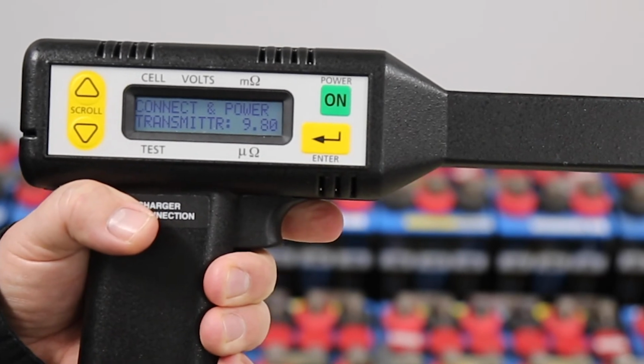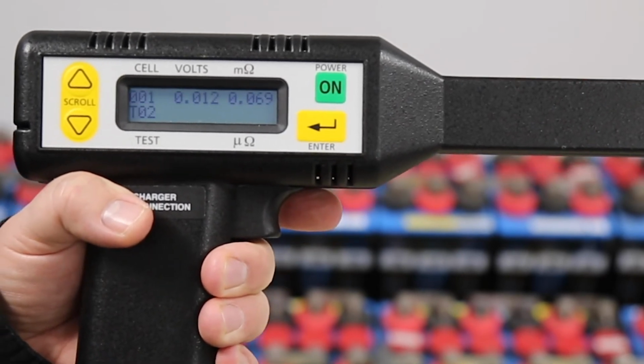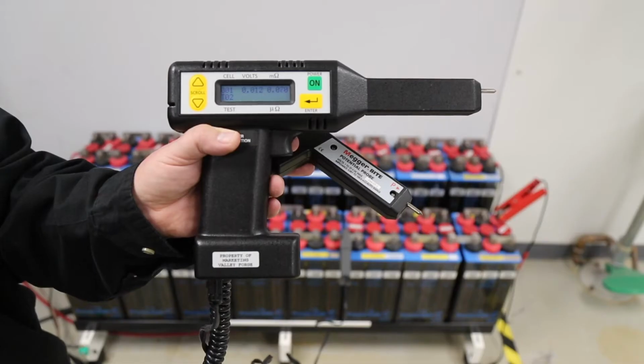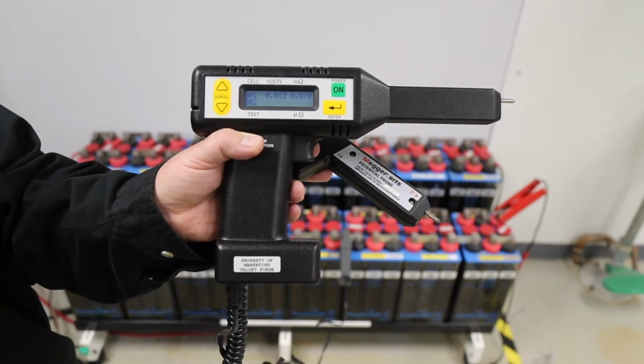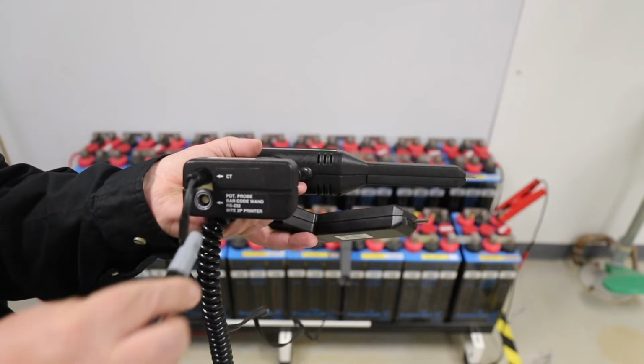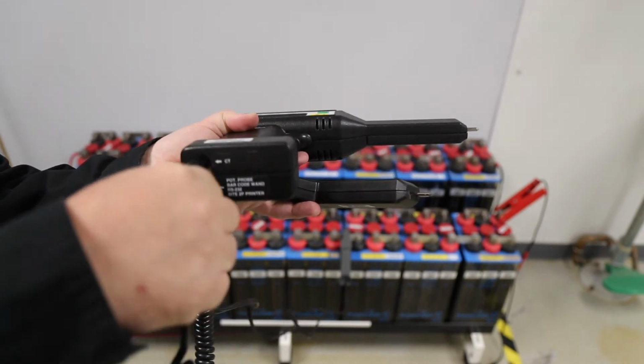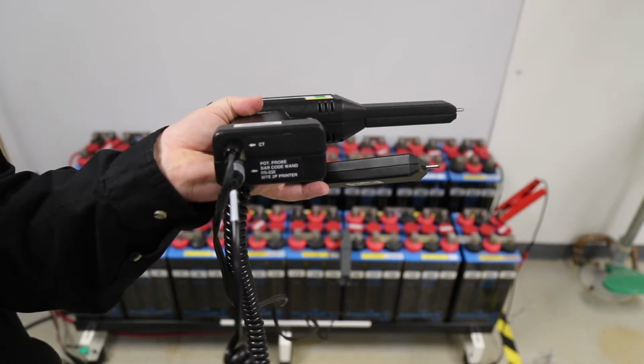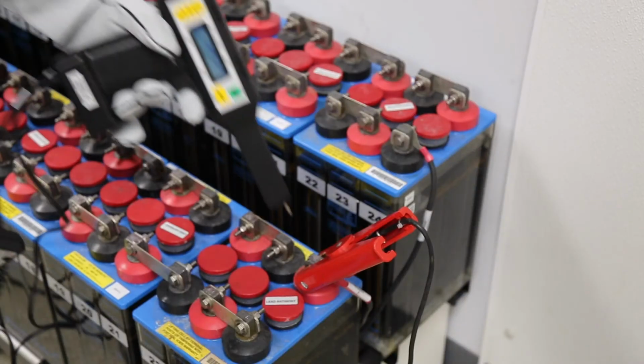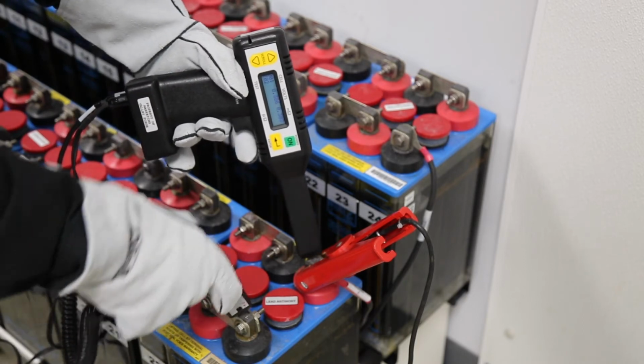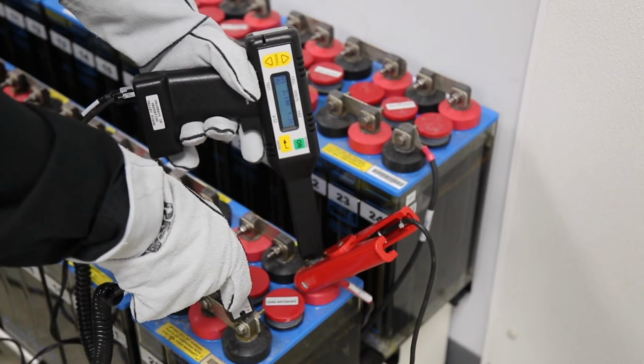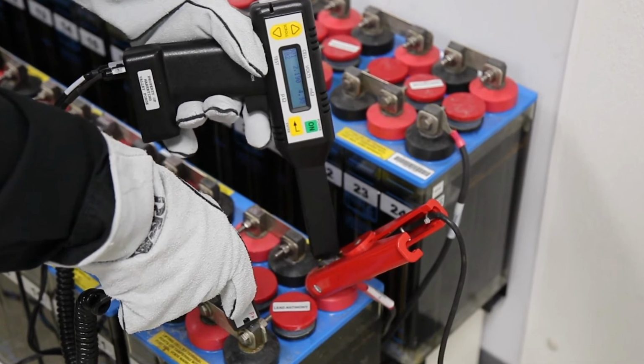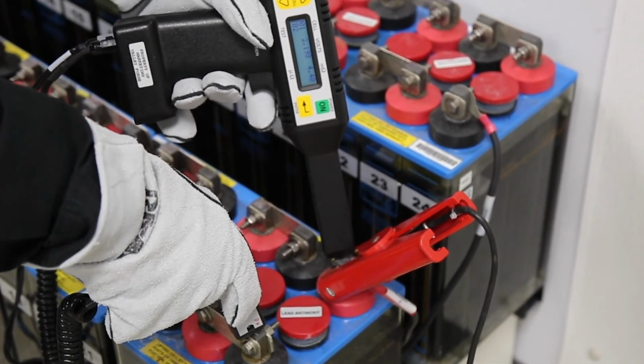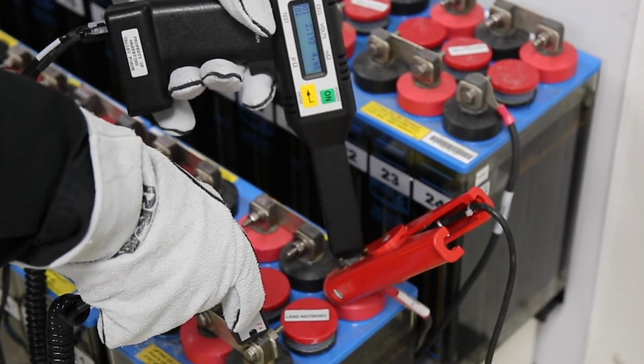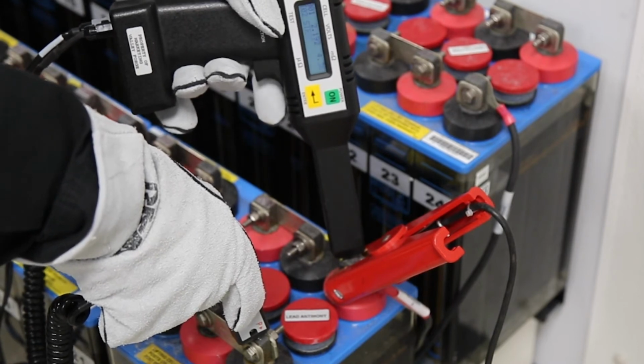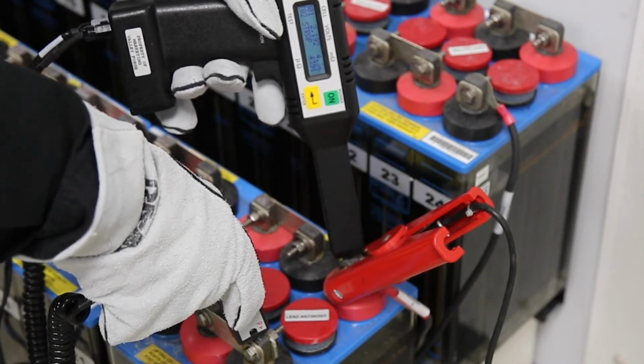The receiver now prompts me to measure the first battery, cell 1. So to measure the first cell, I'm going to first connect the potential probe. I place the receiver across the battery, and I can see the battery voltage and impedance on the display. I now pull and release the trigger to save the value. Note, the actual value is saved when the trigger is released.